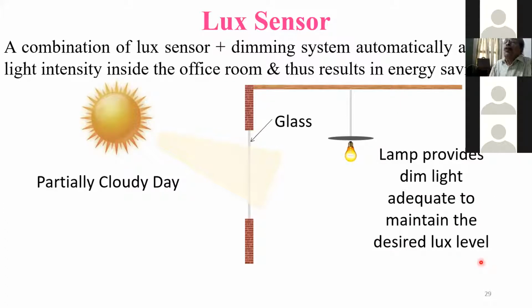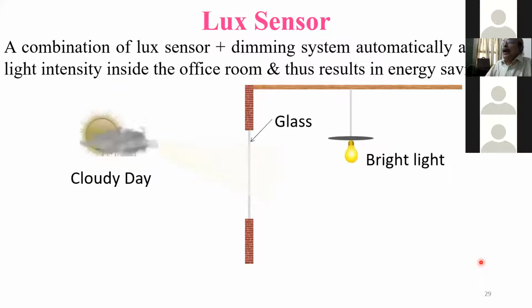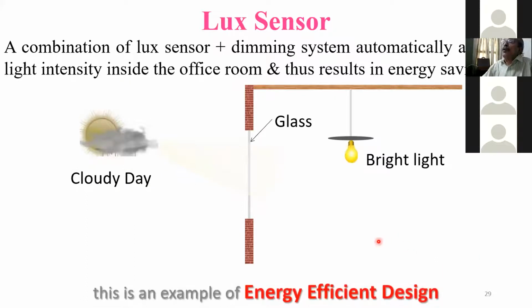Now, if it is a cloudy day, there is no sufficient light at all in the office, then the combination of lux sensor and dimming light will provide a bright light. So the light is made to perform under a dimming condition or full bright condition according to the requirement of your workstation. So that is a saving in electricity towards lighting cost.